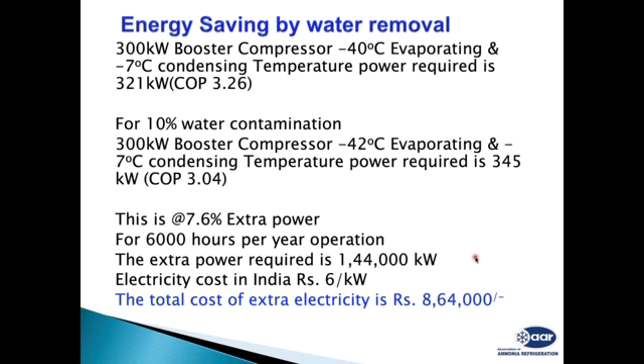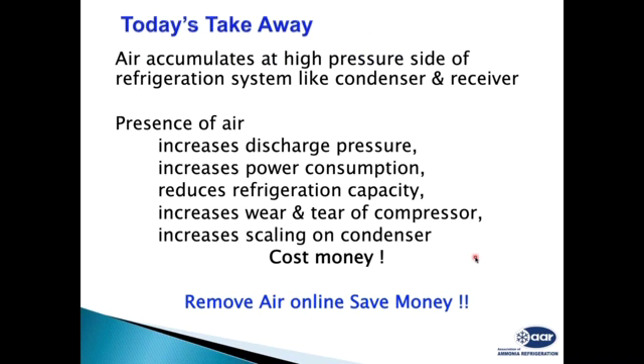So that's all about today's presentation. I'll go through a quick review of what has been talked about today. Today's takeaways: air accumulates at the high pressure side of the refrigerant system, like condensers and receivers. Presence of air increases discharge pressure, increases power consumption, reduces refrigerant capacity, increases wear and tear of the compressor, increases scaling of the condenser, and of course, all this costs money. Now, what I suggest: remove air, and save energy.